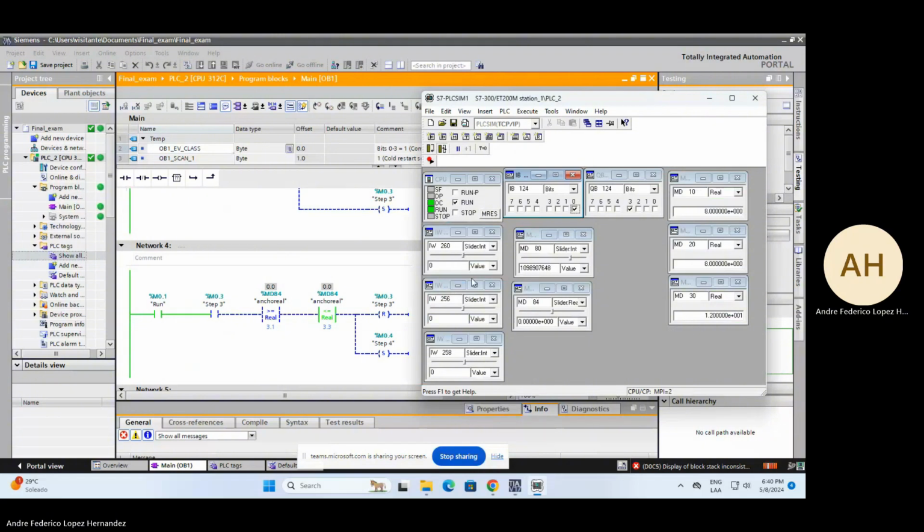To eject the part into the bin, the corresponding eject cylinder control must be turned on for 1 second. The eject mechanisms are each controlled by a single acting air cylinder. The position of a part to be ejected into a bin is determined by its distance from the UX3 ultrasonic distance transducer.